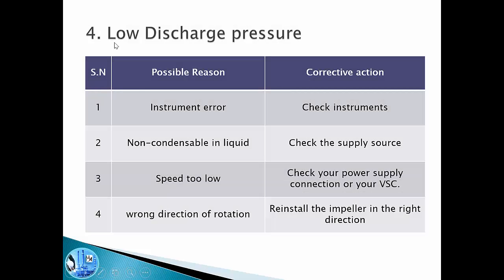The fourth problem is low discharge pressure. The reason could be an instrument error giving misleading readings — we need to check and calibrate our pressure gauges. It could be non-condensables in the liquid, and as mentioned we need to check the supply source, since a mix of gas with liquid will affect pump performance. Maybe the pump is running at very low speed — we need to check the power supply connections or the variable speed controller if one is attached. There could also be a wrong direction of rotation, in which case we need to reinstall the impeller in the correct direction.